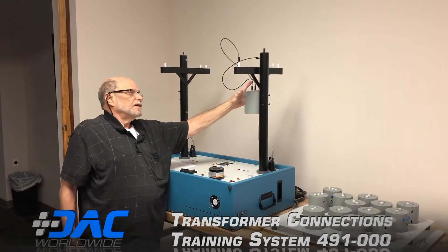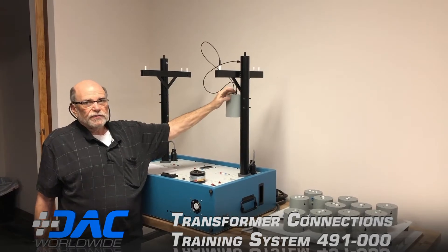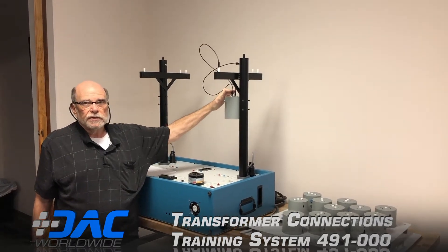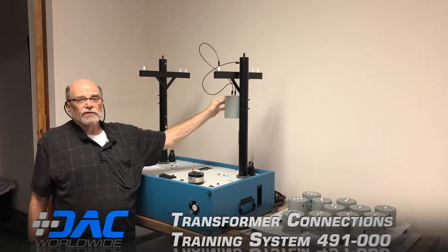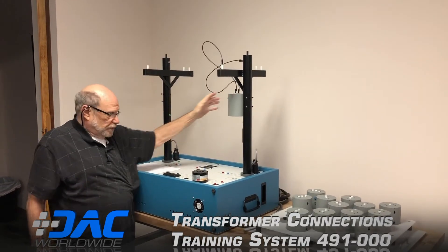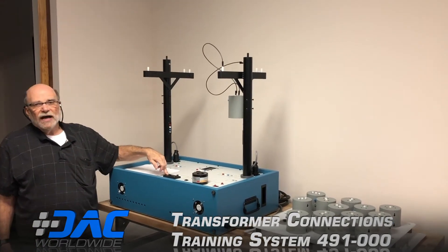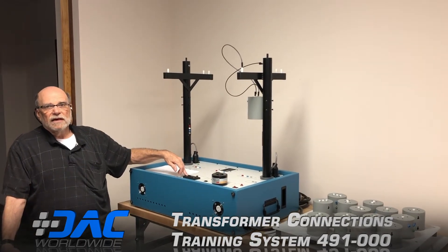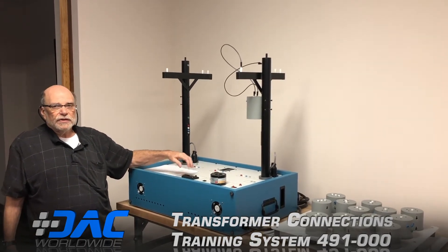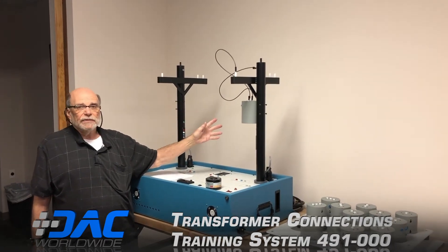When I say this is set up for 2,400 volts in, the actual voltage appearing here is only 24 volts. The actual voltage on the output is 2.4 volts with a center tap to 1.2 volts. The meter has been modified to read 100 times the actual voltage so that it appears to be the right voltage, but it's a very safe unit. There's no shock output hazard at all.